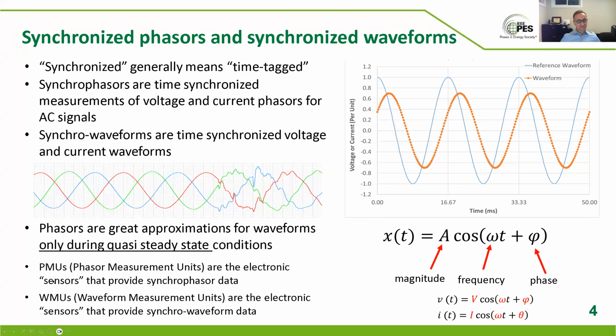A couple of other basic definitions. PMUs are well established as phasor measurement units. They're really synchrophasor measurement units. Otherwise, all relays do measure, but most relays do measure phasors. But we're talking synchrophasor measurement units as PMUs. And not so common, let's call it arbitrary at this time, but maybe over time it becomes standard, is a waveform measurement unit, similar to PMU. That's the device, or function of another device, that basically captures time-tagged synchronized waveform information.